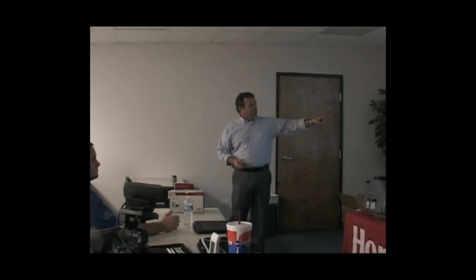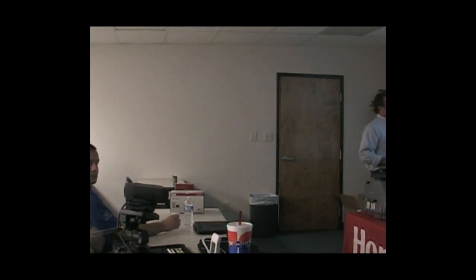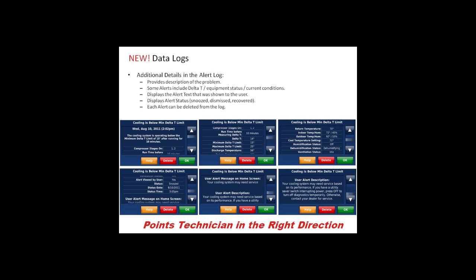So back to alerts log. I like to know when things happen. So I come here and it tells me exactly what happened at my delta T, what time of day, and everything, and told me that the cooling system operated below the minimum delta T of 15 degrees after running for 10 minutes. It's going to point me to my compressor, and I may have a compressor failure.